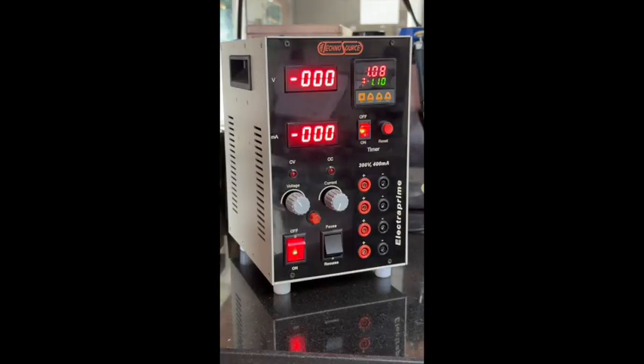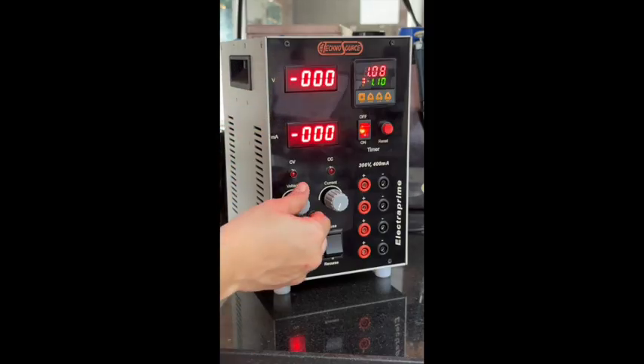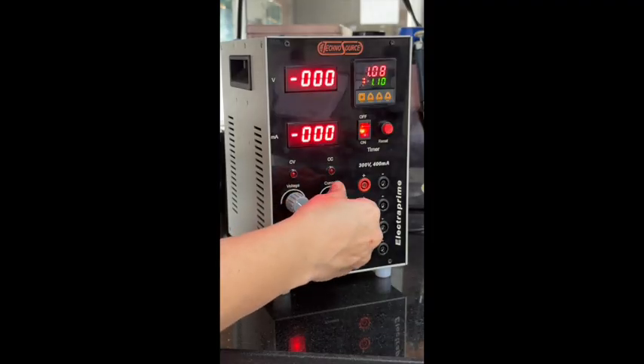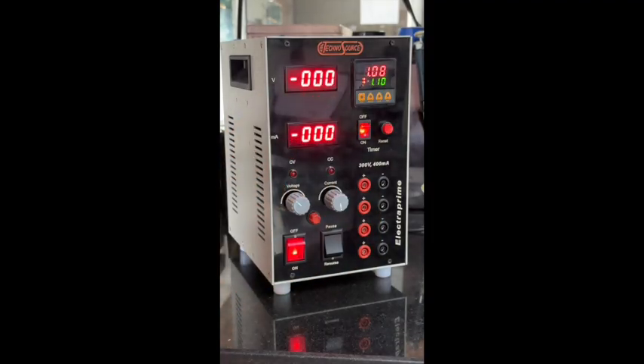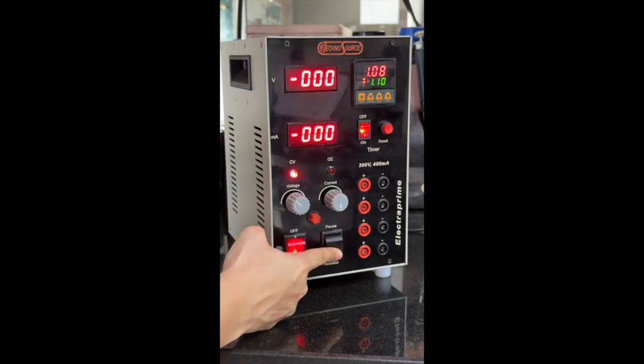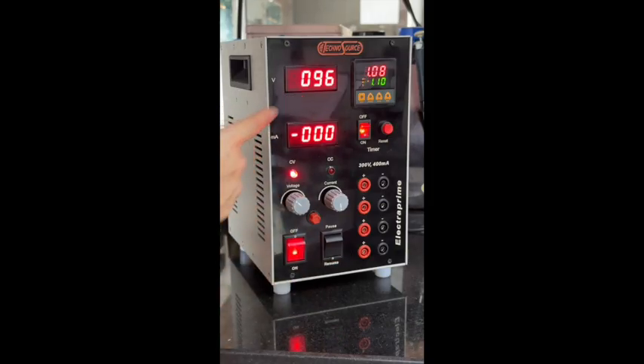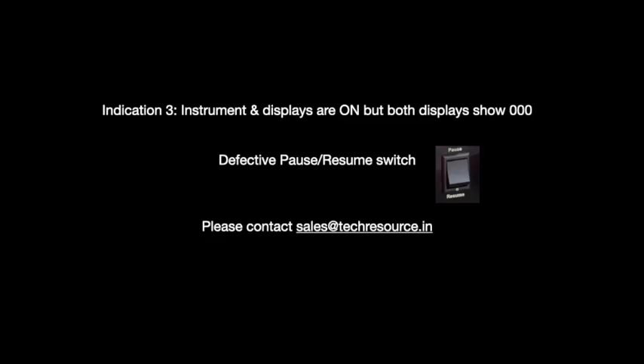Indication 3. Instruments and displays are on, but both displays show 0. You can see here that the mains light switch is on, the light on CV is on, and both displays are on, but both displays show 0, and when both knobs are rotated, displays do not change. The most probable cause for this is that the pause resume switch has been set to pause. You can flip it to resume and the displays should show some values. If this does not happen, most probable cause would be a defective pause or resume switch. This would have to be replaced by us.